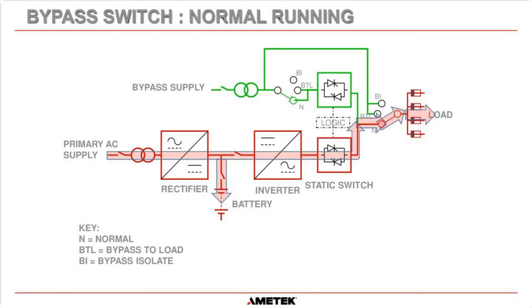So in normal operation, the static switch is going to be on inverter, but the manual bypass switch is going to be in the normal position. So these contacts here are connected. And remember, on the bypass, we do have to get power to the static switch, even though it's not on. So those contacts there are connected as well. There are two sets of contacts inside the manual bypass switch, and in normal operation, they are in the normal position, and that is how it's connected.